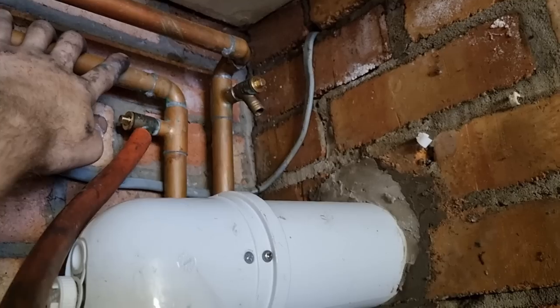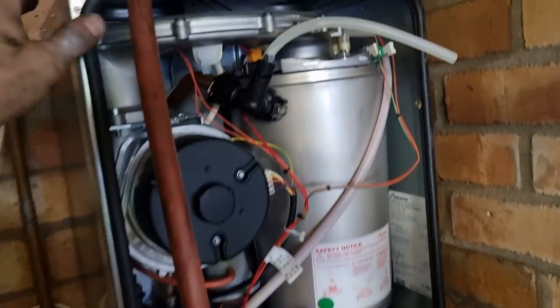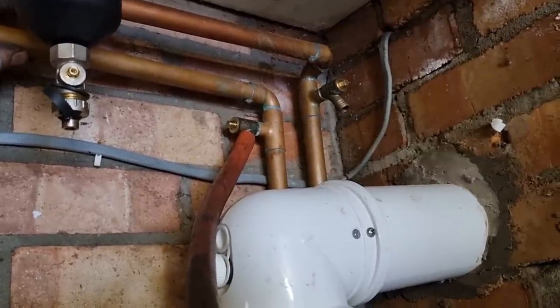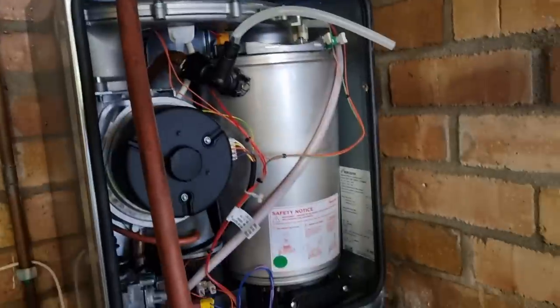And we're getting flow temperature. Perfect. All we'll have to do is check all the rads, have a good tidy up, make sure the case seals are good on the boiler. Might still have a bit of airlock, but at least the pipe's going out. There goes the air gurgling. We'll have a look at it. I'm sure we're getting on the right track now.